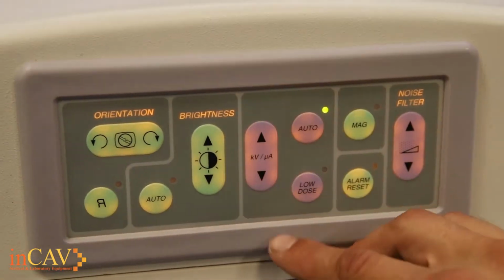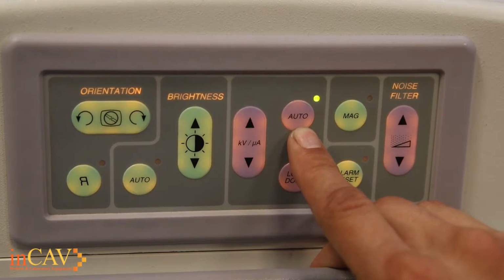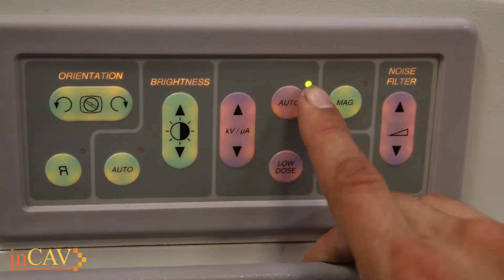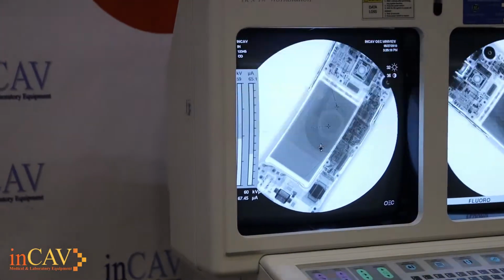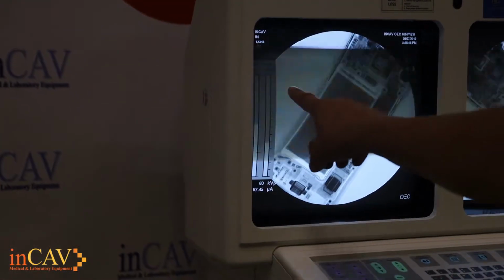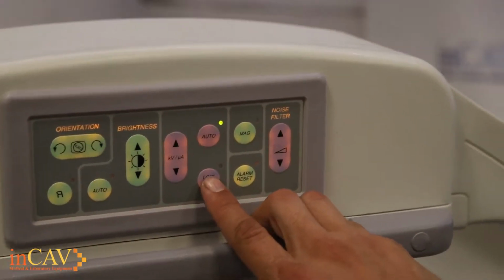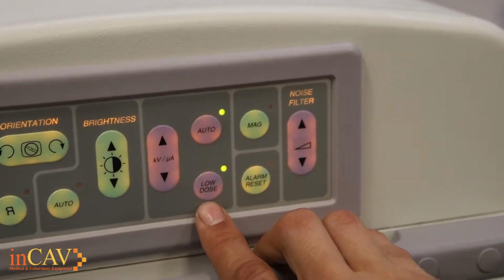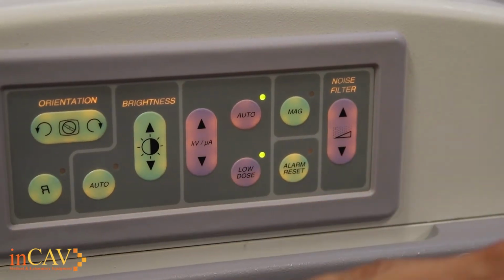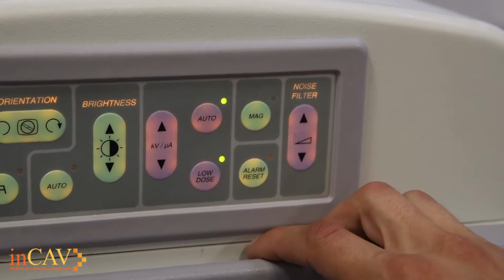As you can see. Now over here is your procedures. Now we have automatic as it stands right now, so it's going to be an automatic kV mA. We can take that off and we can adjust the kV and mA for the procedure you wish to perform. As you can see right there, kV and your mA is being changed. Now most of the time you're going to want to stay on auto, of course, but in certain procedures you might have to change that. Also, we have a low dose mode, which will actually allow you to expose the patient to the lowest amount of dose per exposure level here.